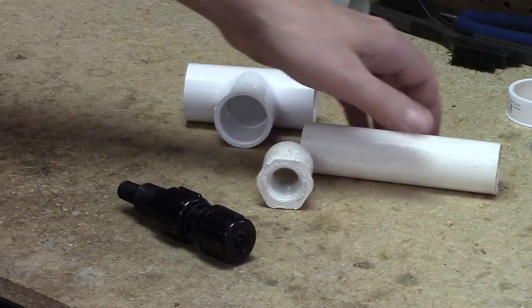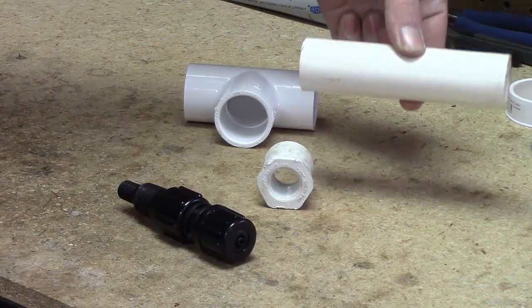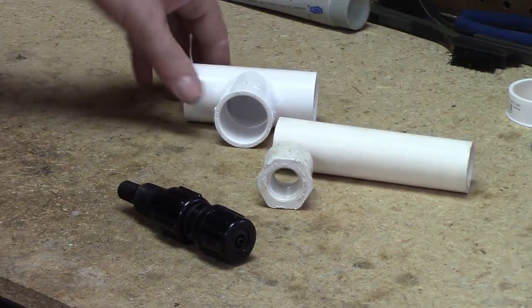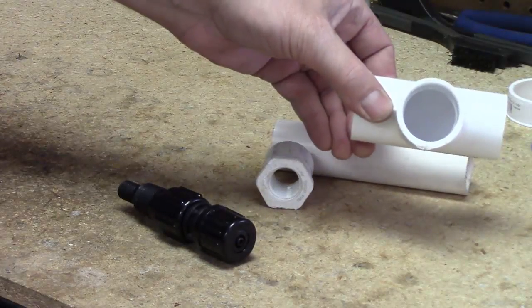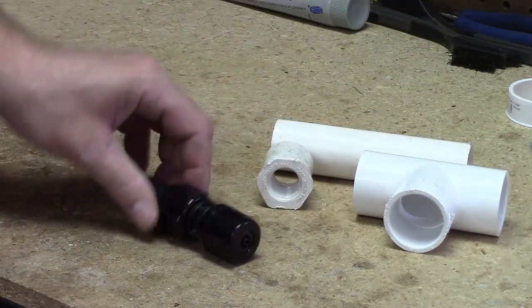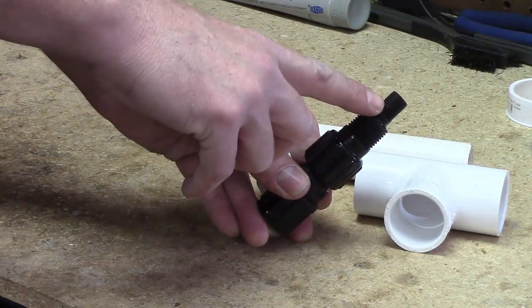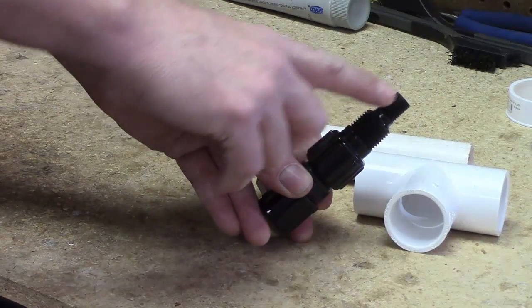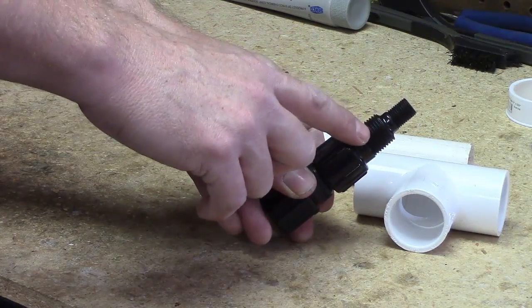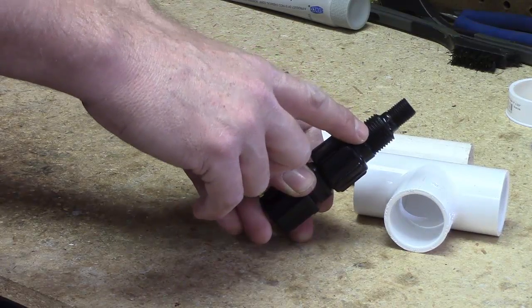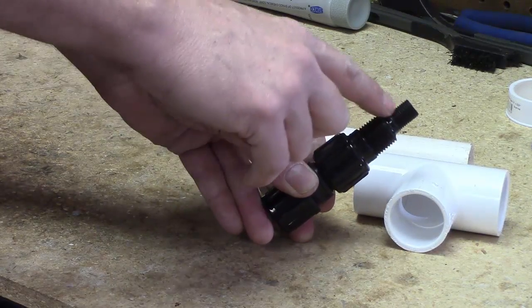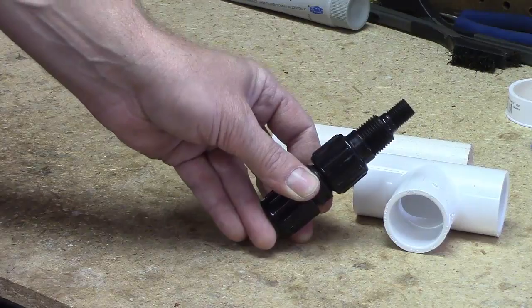The first thing is you'll have your service line, and you'll have to cut your service line and install a T. The T is going to be the same diameter as your service line, but you're going to have to reduce down depending on whether you already have a small service line or not. If you have one inch or three quarter, you're going to bush down to half inch, and if you had half inch piping already, you could bush down to three eighths.